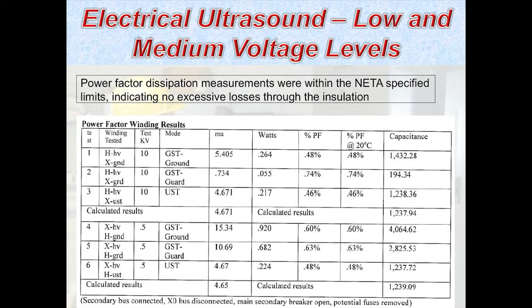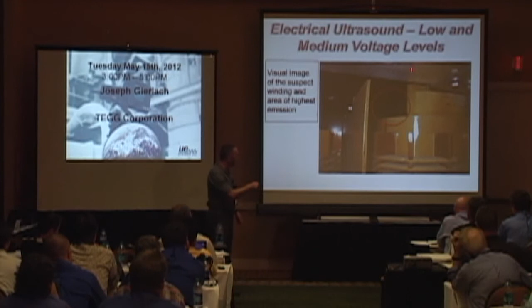What you're looking at is the B-phase coil, with the windings insulated and isolated from each other. You can see the varnish on it and all the shims in between them. This piece going down is the vertical core piece. It goes down inside this winding, and the outer part comprises what we call the secondary, while the internal part comprises the primary windings. Up here is the vertical piece common to all three, joined together in the manufacturing process.